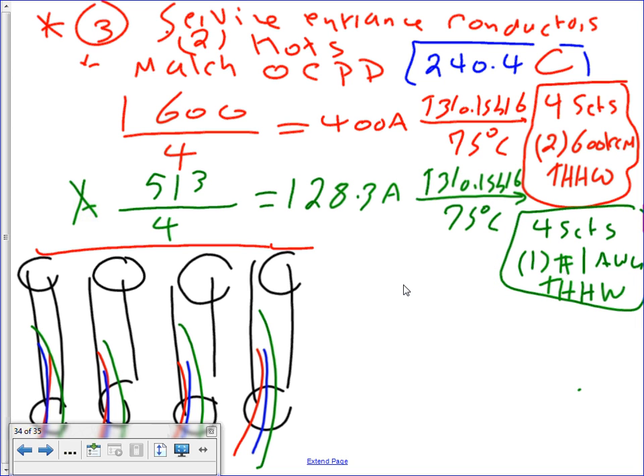Okay. Now, Karen, there's one little problem. Can you parallel number 1? You cannot parallel number 1. The code says, guys, you shall not parallel number 1. The minimum that you can parallel is 1 aught.